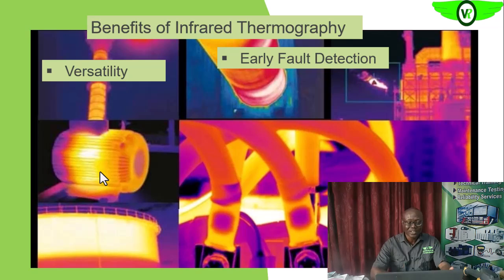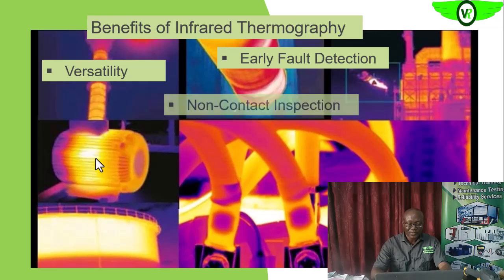you would have seen it using this technology. Like this electric motor, as an example, as we'll see later, the temperature here is a reflection of the winding temperature. So once it's rising beyond a level, we know we're already having issues with the winding. So before the winding fails, you already know. And then if there is any intervention or maintenance strategy that you want to deploy to bring it back to what is normal, of course, we will do that.